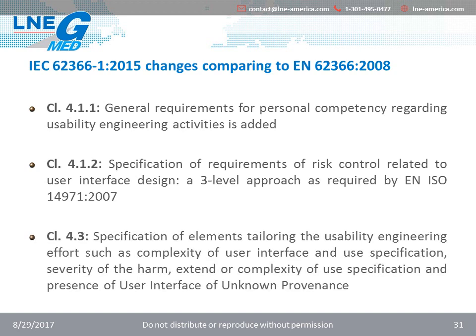Clause 4.3, some elements tailoring the usability engineering effort have been specified in this clause, such as complexity of user interface and use specification, severity of the harm, extent or complexity of use specification, and presence of user interface of unknown provenance.